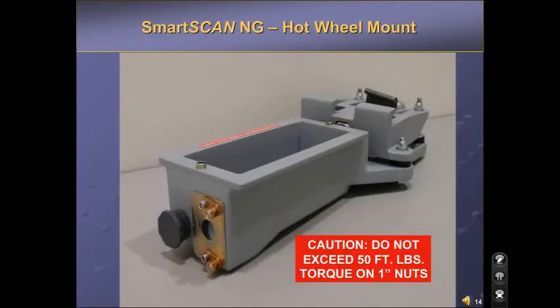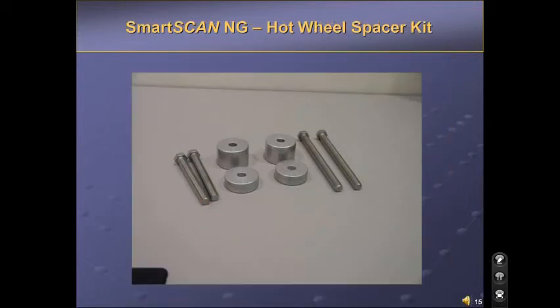As with the bearing scanner mount, there is also a cautionary label on top of the hot wheel mount that says, "Do not exceed 50 foot-pounds of torque on 1-inch nuts." The hot wheel mount provides for 2 grounding connections and has an opening for an airline attachment. This spacer kit is provided with each hot wheel mount. It should only be necessary to use this kit at locations running 115-pound rail.